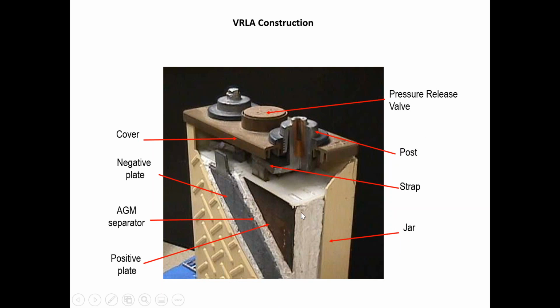Now, this is what I was talking about. This white material is a glass mat separator. So it's a spun porous material that actually has the acid absorbed into it. So the separator not only keeps the positive and negative plates from shorting against each other, it also retains the electrolyte. Now, keep in mind, these plates are also a grid design. They're pasted plates, and the paste material is usually a lead calcium alloy compound, and it's very porous. So the acid or electrolyte is actually also absorbed into the plates as well. So you're looking at a light gray negative plate, and the positive plates are the darker lead oxide material.